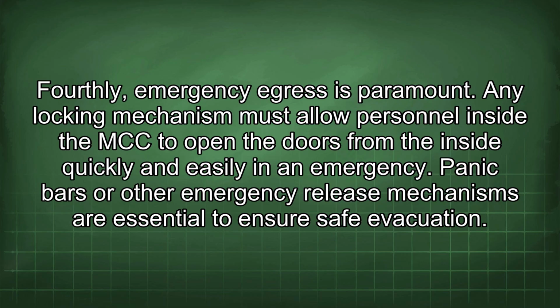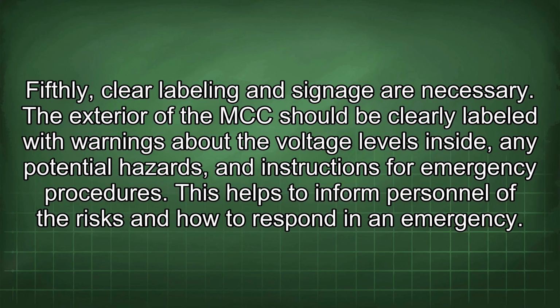Fourthly, emergency egress is paramount. Any locking mechanism must allow personnel inside the MCC to open the doors from the inside quickly and easily in an emergency. Panic bars or other emergency release mechanisms are essential to ensure safe evacuation. Fifthly, clear labeling and signage are necessary. The exterior of the MCC should be clearly labeled with warnings about the voltage levels inside, any potential hazards, and instructions for emergency procedures. This helps to inform personnel of the risks and how to respond in an emergency.